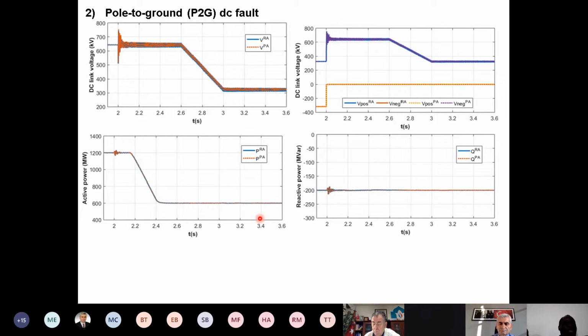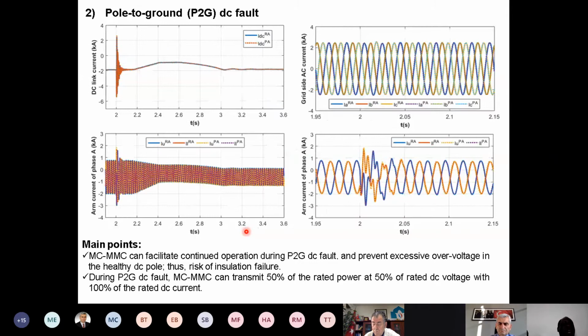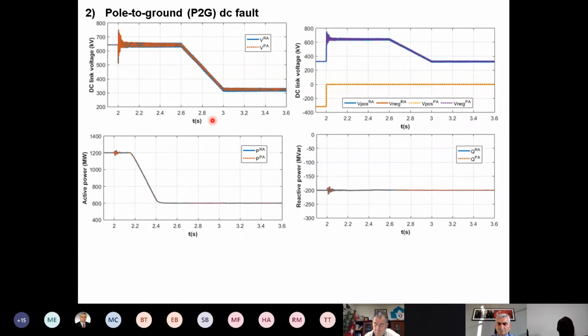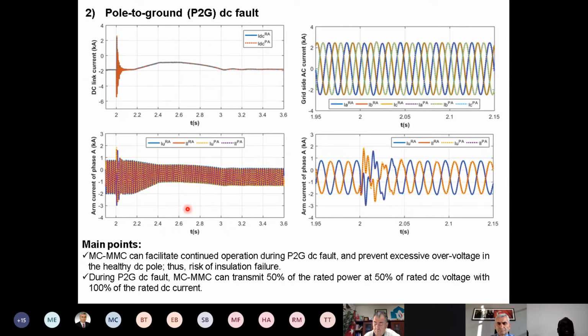I think maybe this is in the other plot. Yeah, and you can see here the DC current. So in this case, with 50% of DC voltage, we can deliver 50% of the active power with the rated current, as you can see from this plot here. And you can see all the other things, the grid current remained like nothing happened. And these are the arm currents.